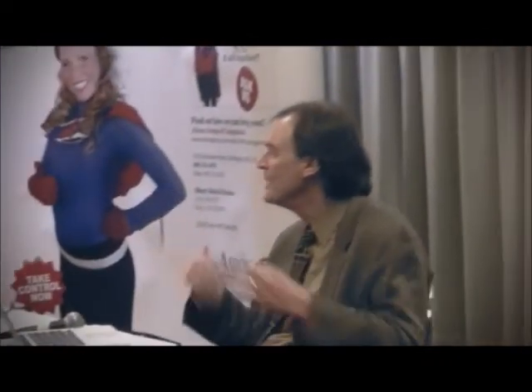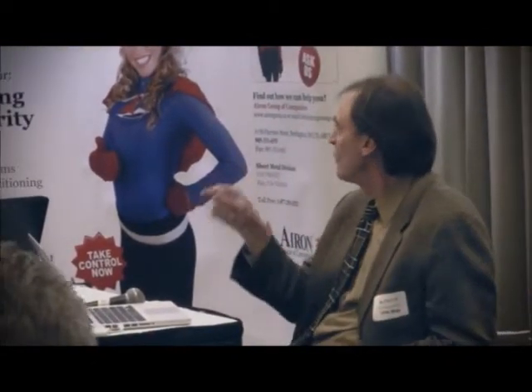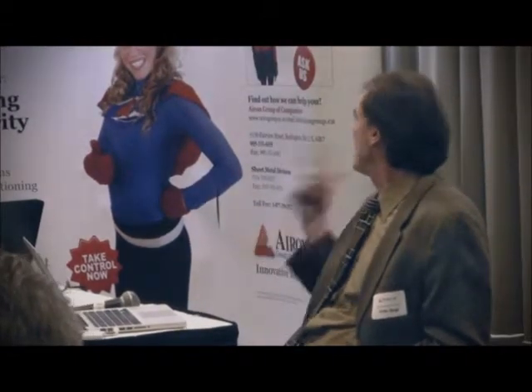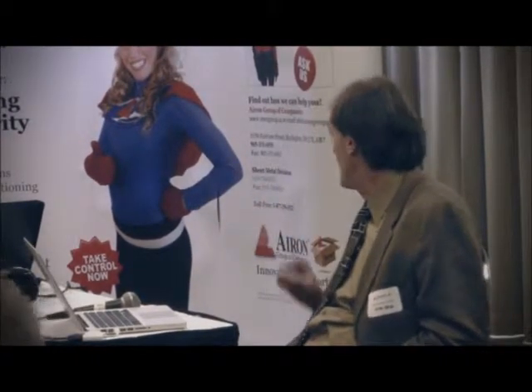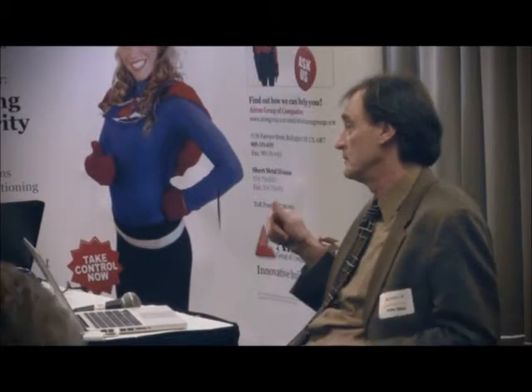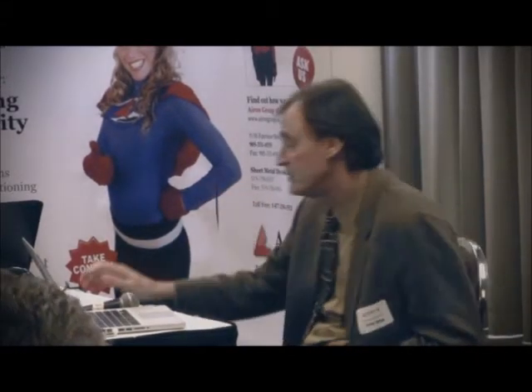Let's look at the help. Outside air damper stuck open. What it says is the damper should be closed, but the system is looking at the temperature differential between mixed air and return air and saying, hey, you can't achieve that if you don't have outside air coming in. We're running an algorithm against data that's sitting there. It didn't produce an alarm, it's a pattern in the data. So we're drawing in outside air. We may think that damper's closed, the command signal out of the BAS may be to close it, but it's open. We're drawing in outside air.